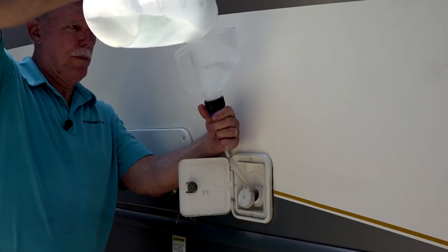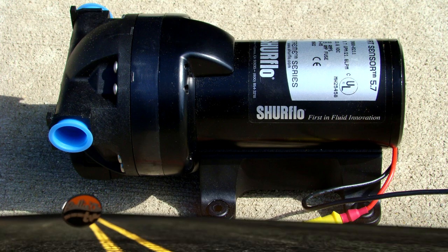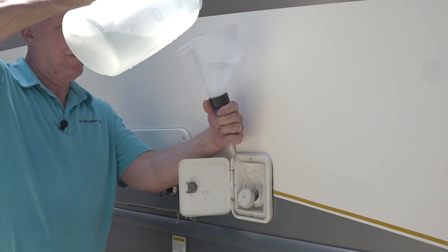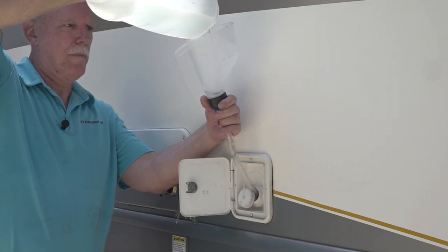Now we can discuss some easy preventive maintenance steps to keep the pump working. RV water pump preventive maintenance is simple — it primarily consists of keeping the water system sanitized and periodically inspecting and cleaning the strainer. Shurflo, a leading water pump manufacturer, stated that a lack of sanitizing the water system is the number one reason for premature pump failure and poor performance over time.